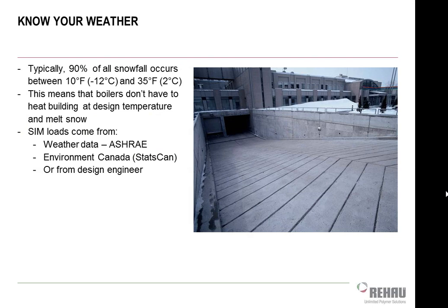The other reason I mentioned the temperature not having very many snowfall hours when it's below 10 degrees outside is because we typically have to size our boiler plant for a 0 degree or -5 or -10 degree day or whatever your design condition is where you're at. But I don't really have to have it do all the space heating of the building and the snow melt at the same time, because it's probably not going to be able to snow when it's below 0 degrees outside. So I can size my boiler for the building for what its loads are at its design temperatures, and I don't have to upsize it to do the snow melt. I just have to have a heat exchanger sitting over here on the side, so I can send some water over there to the heat exchanger for some moments in time to go melt some snow.